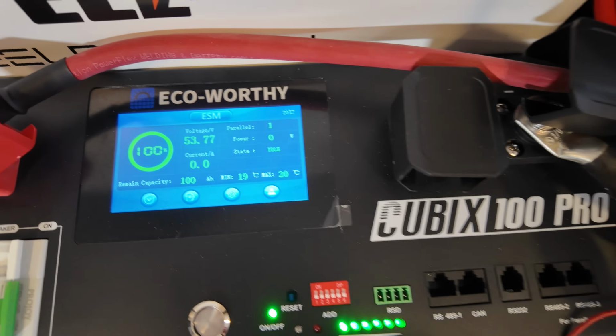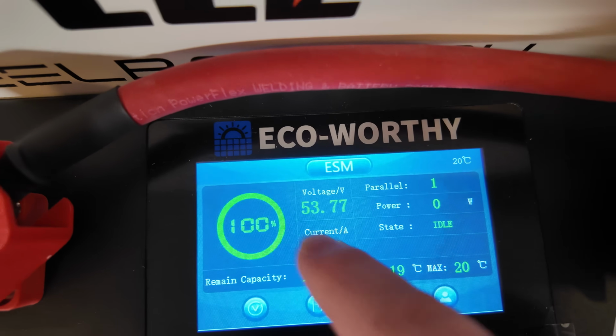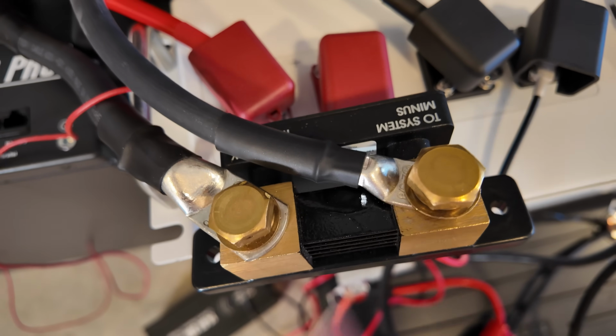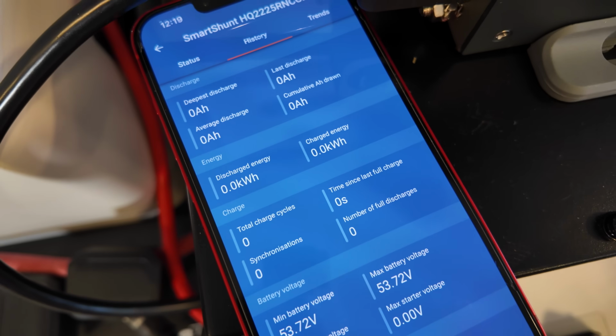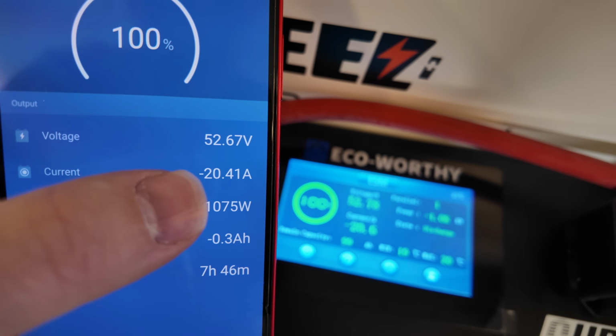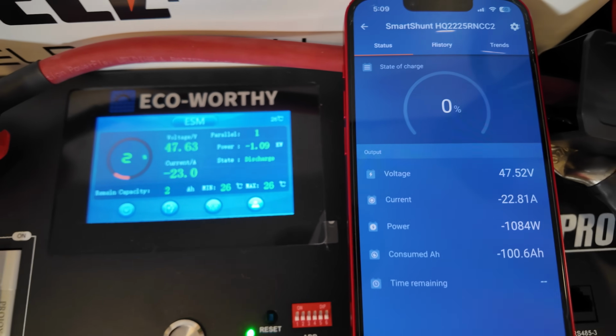Capacity test time. You can see we're at 100% state of charge. We're going to be metering the power through the Victron Smart Shunt here, and you can see everything is zeroed out, and we're pulling almost exactly a 0.2C rate, 20 amps here.